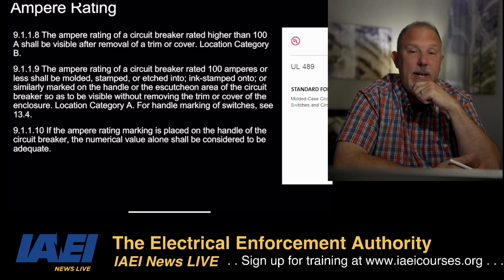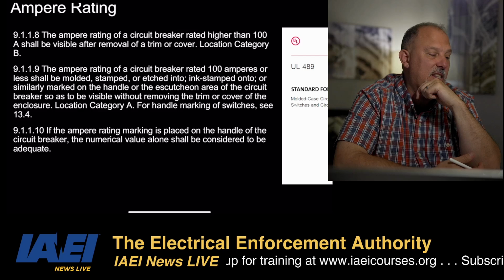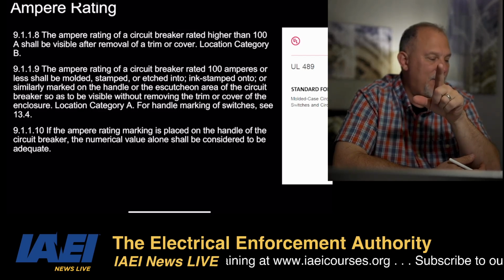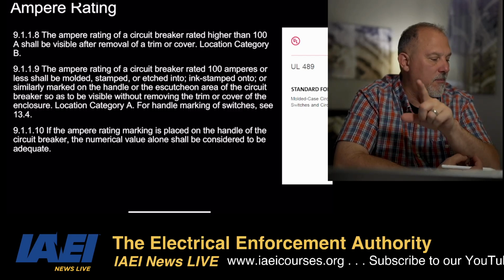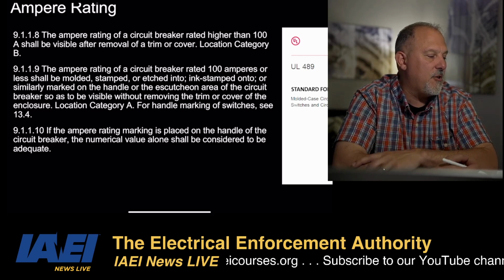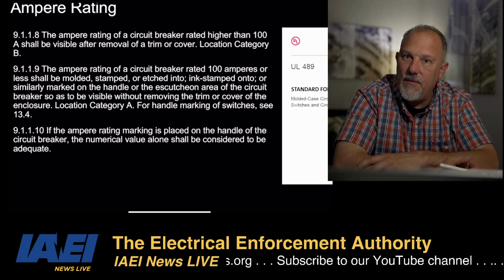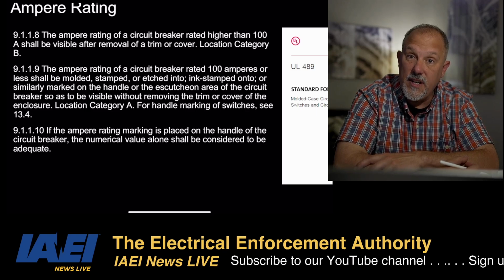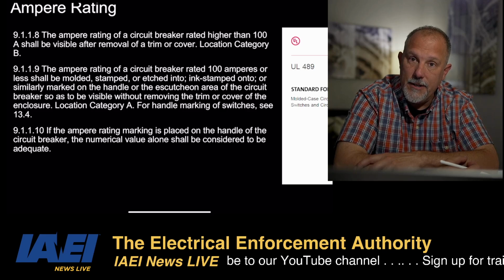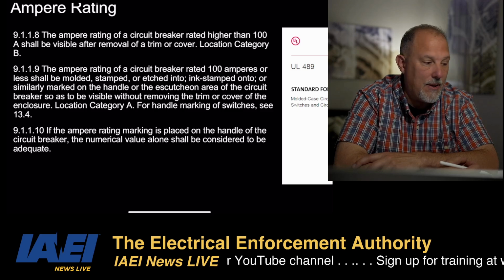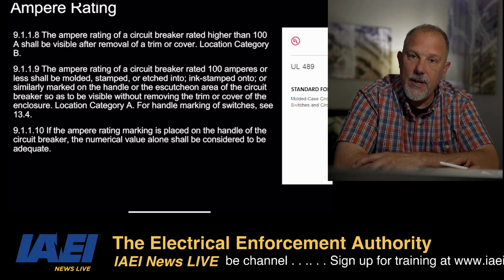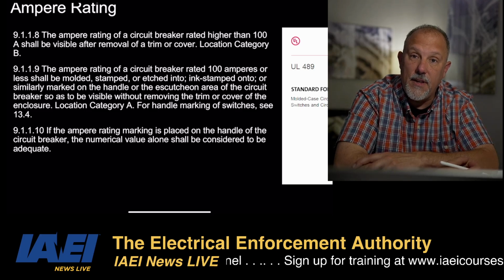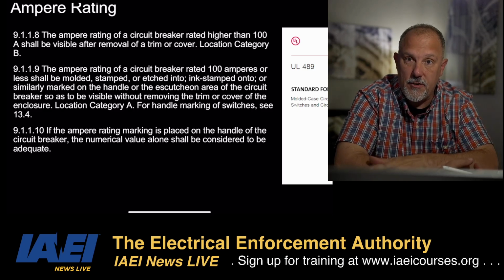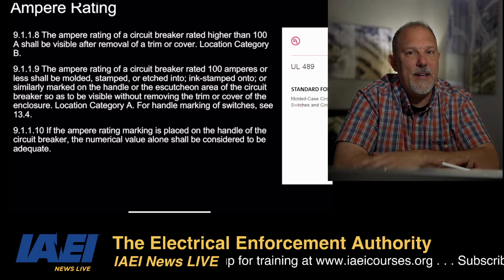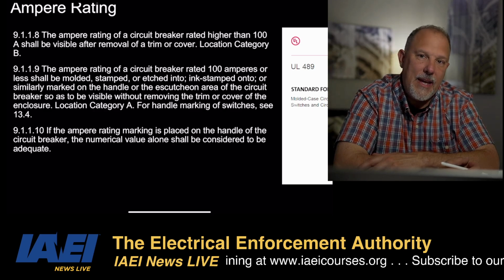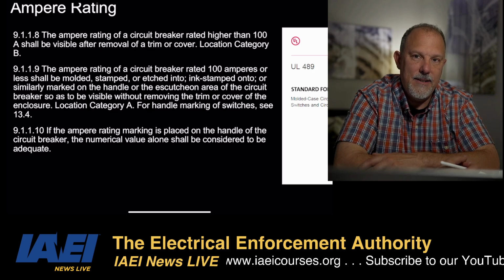The Ampere rating of a circuit breaker rated 100 amps or less has to be molded, stamped, or etched into, ink stamped, or similarly marked on the handle or the escutcheon area of the circuit breaker. So this is location category A. We've got to be able to see this through the dead front. If you look at any residential panel board, that's where you're going to see a lot of the 100 amps or less, right? You have to be able to see that. It's typically going to be on the face of the handle. You'll see that on the bigger breakers too, but you'll always see 100 amps or less on the handle. It's going to be visible with the dead front on. If you can't see the label for the Ampere rating, you may have to remove the dead front.